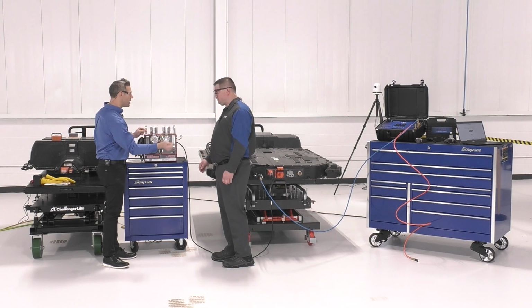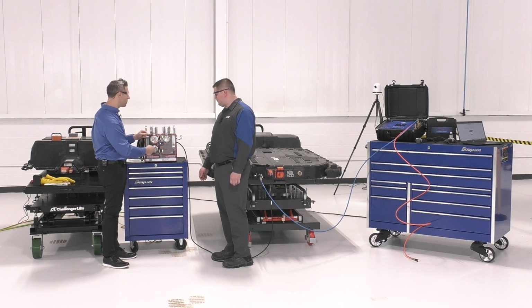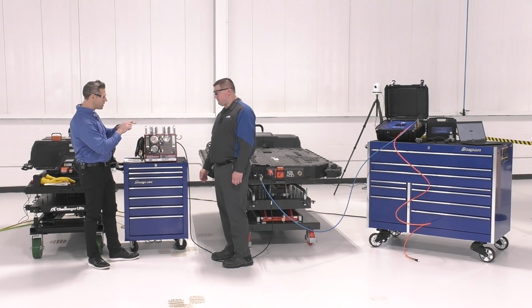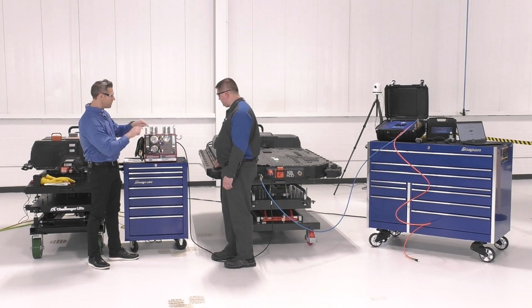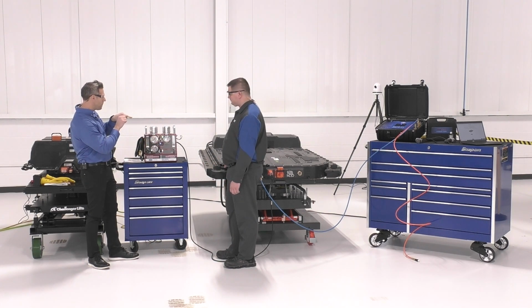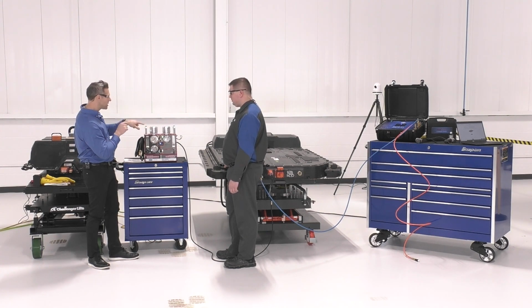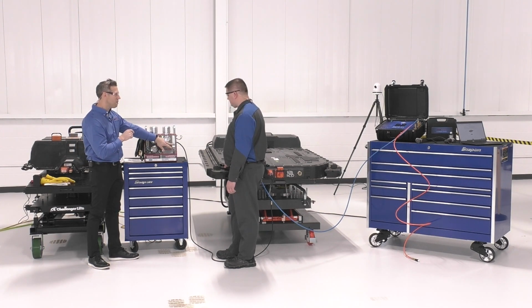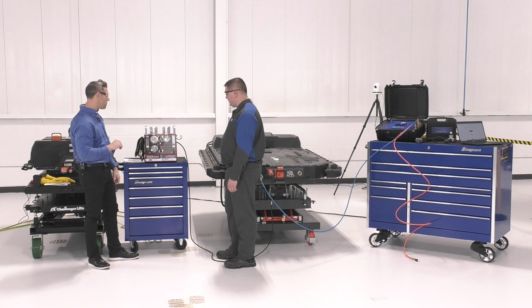Because you're going to be pressurizing the enclosure, adding a lot of flow to it, what you're looking for in this test is making sure the ball drops down so that the flow out of the battery doesn't exceed what you'd see as a zero on this gauge. That's how you pass or fail this test.